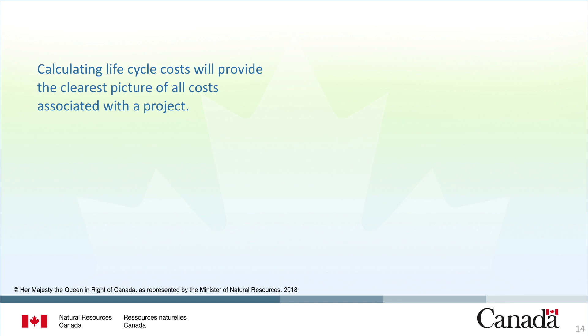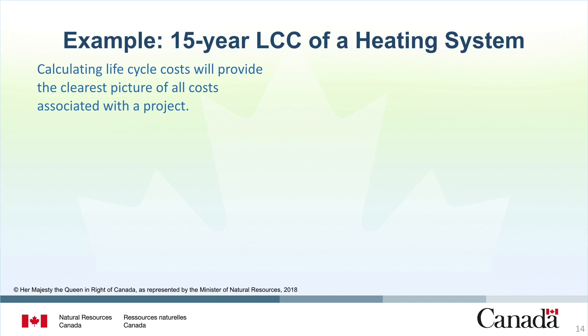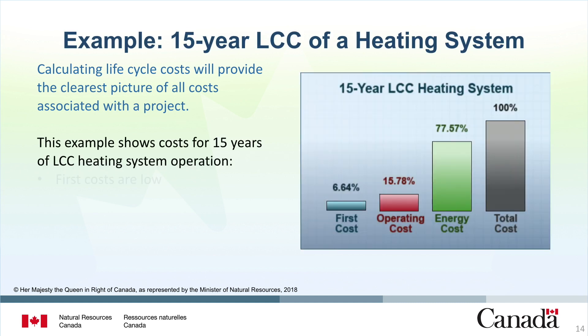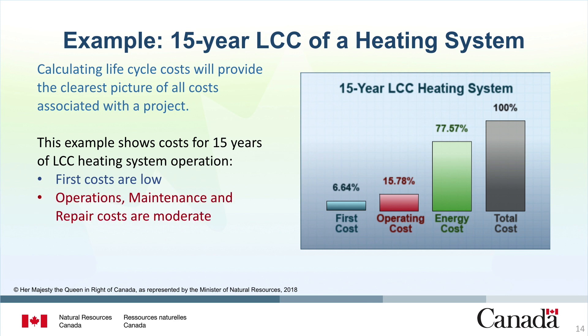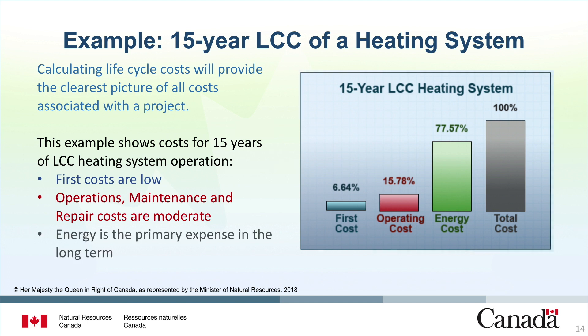Calculating lifecycle costs will provide the clearest picture of all costs associated with a project. For example, with a heating system over a 15-year period, the initial purchase cost is only about 7% of the overall cost, maintenance and repairs account for approximately 16%, but energy consumption accounts for 78% of overall costs. You can see it is critical to understand all costs associated with the lifecycle of the project — first costs can often be just a small part of the bigger picture.